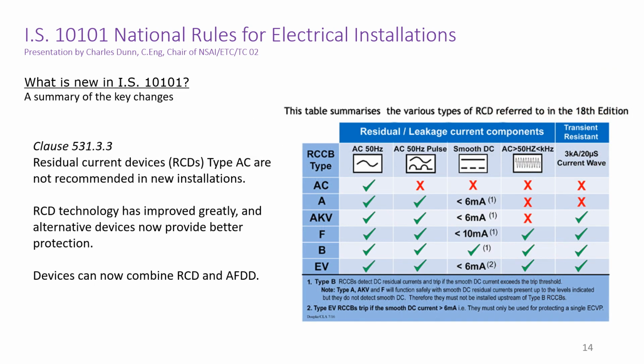Moving on to RCDs, which were once seen as the new technology. In the beginning, residual current devices, RCDs, or earth leakage circuit breakers, ELCBs, as they were called then, were a great unknown in the electrical industry. We didn't know how to wire them and they had a tendency to trip. But eventually we learned that they were of course tripping on small earth leakage fault currents that previously went undetected. Now residual current devices are trusted safety devices, saving many lives.